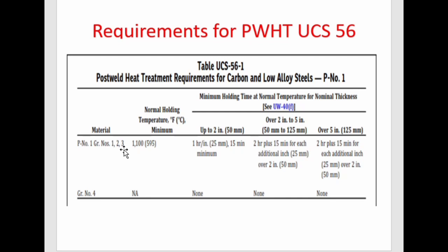Table UCS-56-1 is for P-Number 1, Group Numbers 1 to 3 material, and gives the minimum soaking temperature for different material thicknesses. For up to 2 inches: 1 hour per inch with a 15-minute minimum. For over 2 inches to 5 inches: 2 hours plus 15 minutes for each additional inch over 2 inches. For over 5 inches: 2 hours plus 15 minutes for each additional inch.